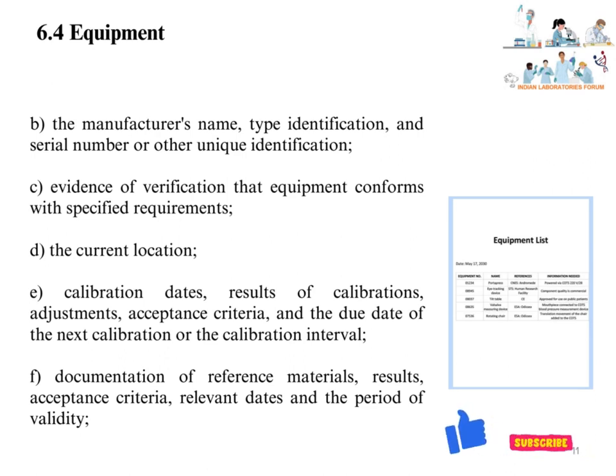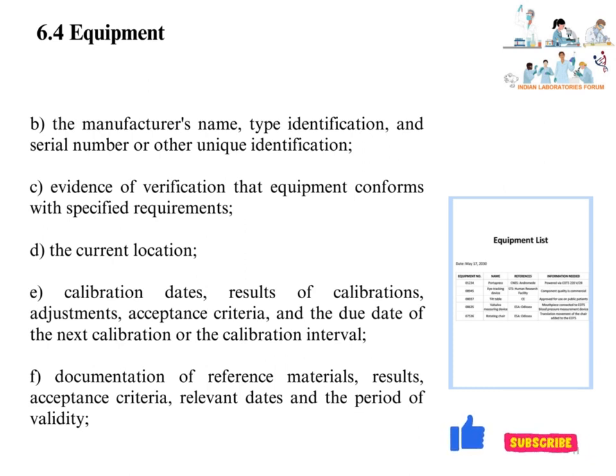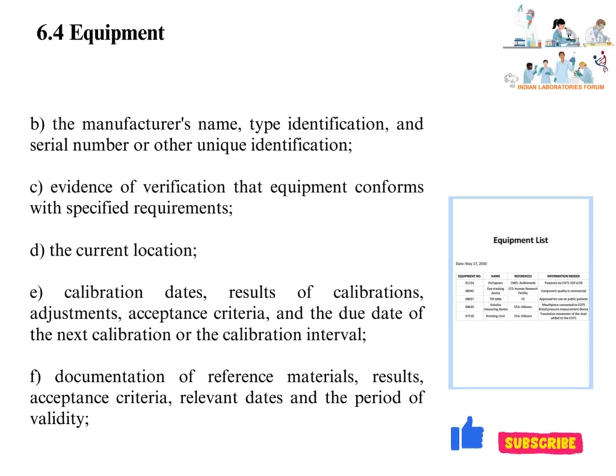Records shall also include the current location of the equipment in the laboratory; calibration dates, results, adjustments, acceptance criteria, and the due date of the next calibration or calibration interval — covered in the calibration schedule and respective calibration records; and documentation of reference materials, results, acceptance criteria, relevant dates, and period of validity, including reference standards used for calibration.